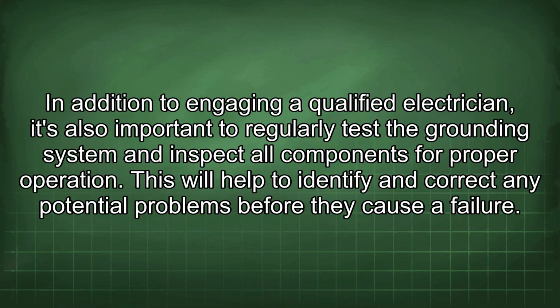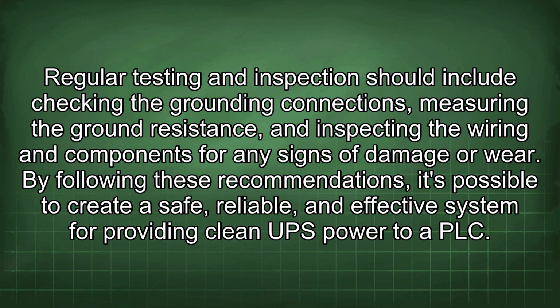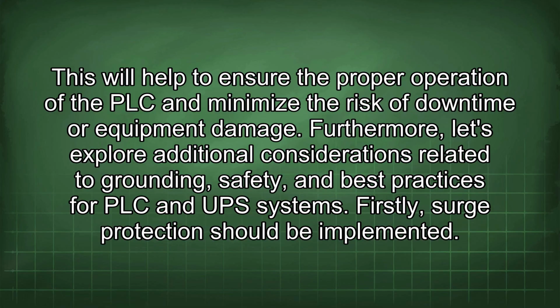In addition to engaging a qualified electrician, it's also important to regularly test the grounding system and inspect all components for proper operation. This will help to identify and correct any potential problems before they cause a failure. Regular testing and inspection should include checking the grounding connections, measuring the ground resistance, and inspecting the wiring and components for any signs of damage or wear. By following these recommendations, it's possible to create a safe, reliable, and effective system for providing clean UPS power to a PLC. This will help to ensure the proper operation of the PLC and minimize the risk of downtime or equipment damage. Furthermore, let's explore additional considerations related to grounding, safety, and best practices for PLC and UPS systems.